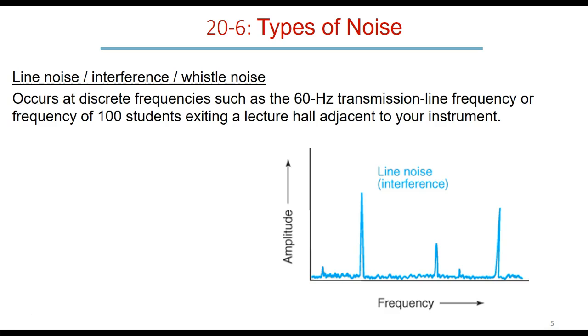It's because of this type of noise. You'd never want to install one of these instruments, say, over by Ragsdale, right? When you've got a lot of movement and big lecture halls. So we have to think about where we're going to place an instrument, how much traffic it's going to get, and how often, say, people are opening doors, big herds of people are walking by, all kinds of stuff.